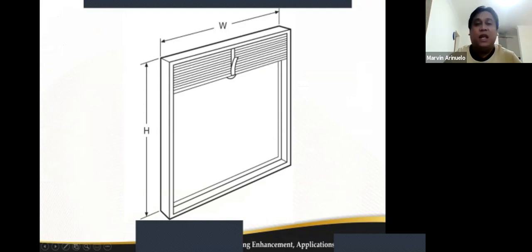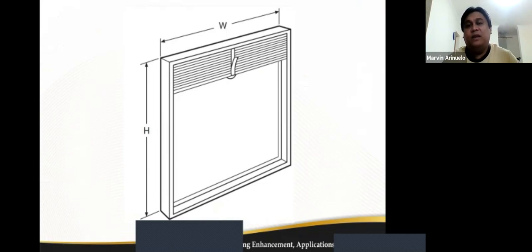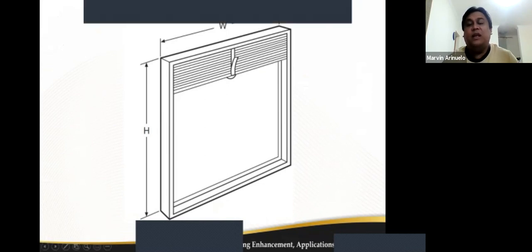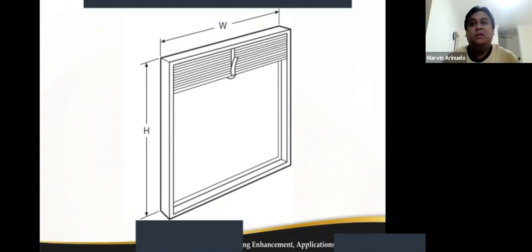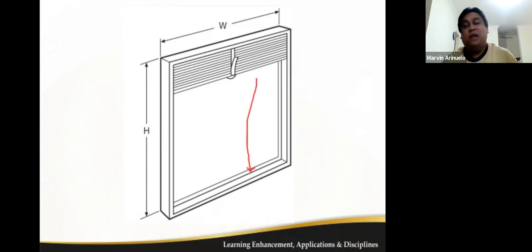And this is how a typical manually operated fire damper looks like. Manually means there is a holding locking device here that will melt if a certain temperature is reached. So automatically this shutter will go down, so it will again prevent the spread of fire from one area to another area. Okay.